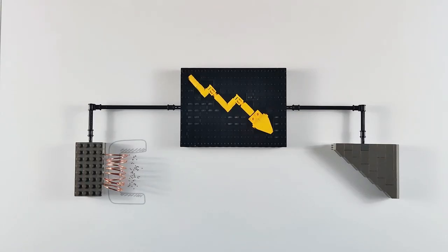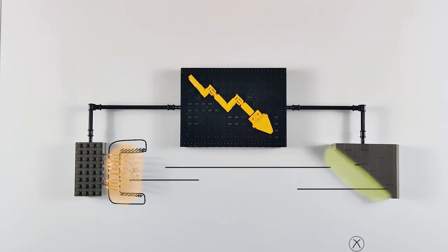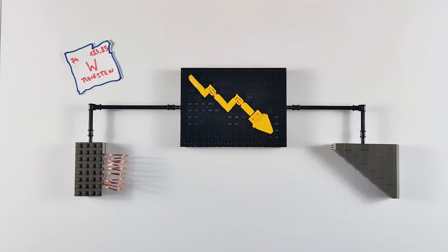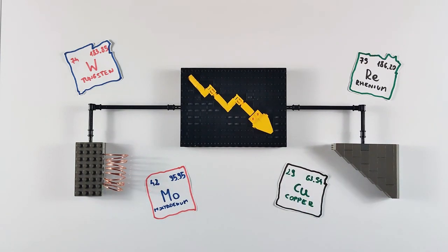But let's get back to the anode. Because it is constantly hit by electrons, its surface temperature can reach over 2000 degrees Celsius. That is why the anode is made of materials with high melting temperature, for example tungsten or rhenium and materials that can efficiently carry away heat, such as copper or molybdenum.